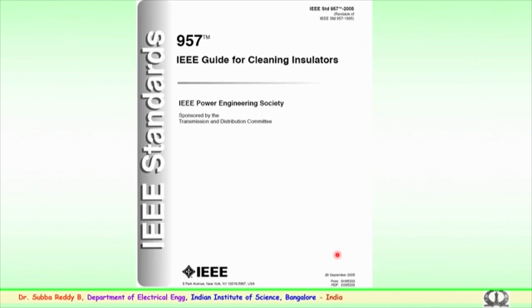Earlier I mentioned the importance of pre-maintenance, or maintenance before the monsoon, where this pollution activity causes flashover. So, there are standards for this. One of the standards is IEEE standard 957, which provides guidelines for the cleaning of insulators, ceramic and glass as well as polymer insulators.